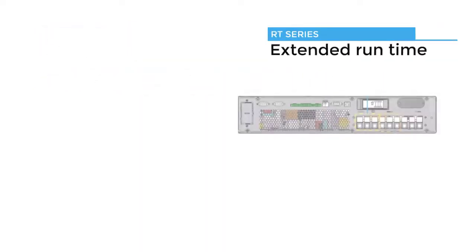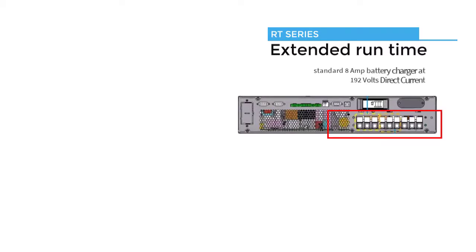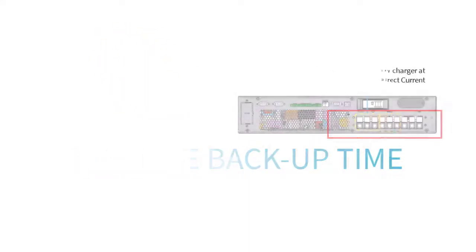The extended runtime machines come with a built-in standard eight amp battery charger at 192 volts direct current, so that you can easily charge bigger amp hour batteries to get longer backup time. Extended runtime machines give you more flexibility when it comes to backup time.